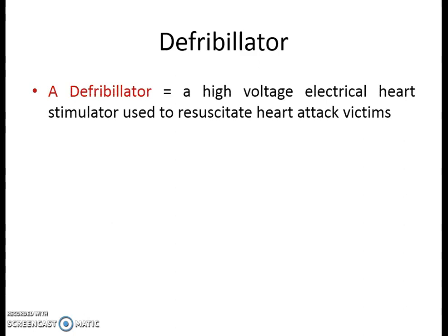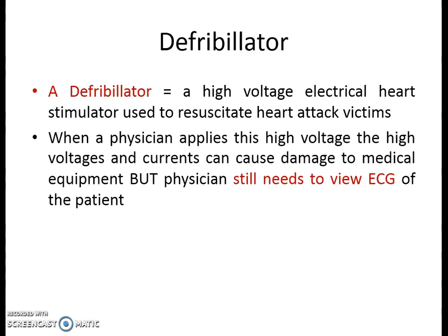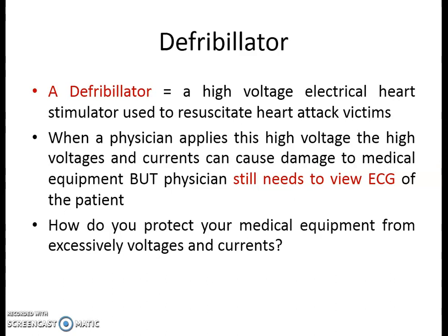The defibrillator is a machine which is used to deliver a high voltage electrical shock to the patient's body while the patient is suffering from a heart attack. Whenever the physician applies this high voltage to the patient's body, this high voltage can damage the equipment. Still, the physician needs to look at the ECG of the patient, meaning the defibrillator is used while coordinating with the patient's ECG. In this case, we need to provide protection to the ECG machine, and this protection is generally provided by means of three mechanisms.